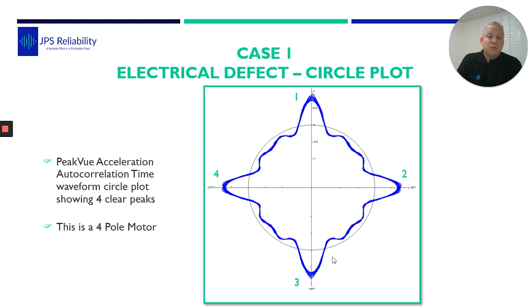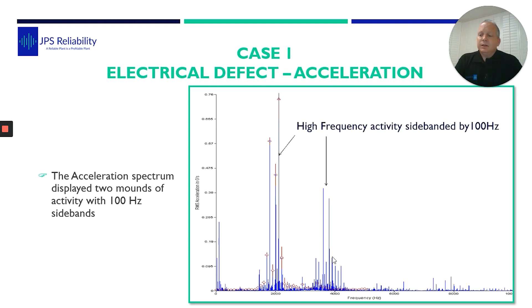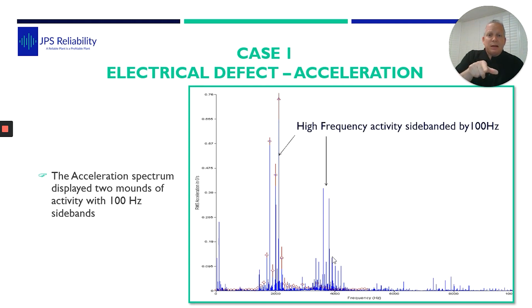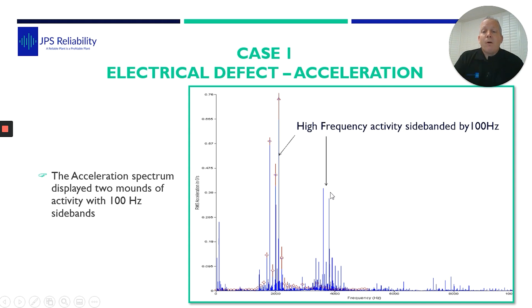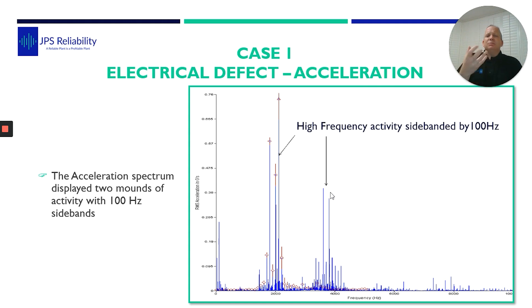Coincidentally, it's a four-pole motor. This is the acceleration data, where we have two mounds of activity, and this is side-banded by 100 hertz. And there's a point where you need to use your common sense.